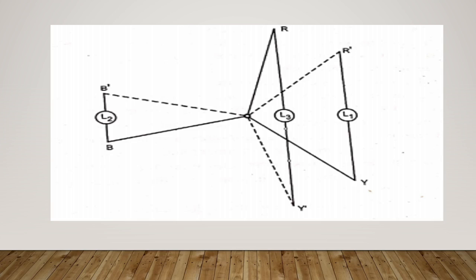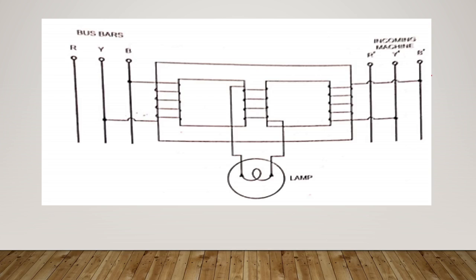Another method of synchronizing is with the help of one three-limbed transformer and a lamp, with the two primary windings on the outer limbs connected to the bus bars and the incoming alternator respectively, and the secondary winding on the central limb, like this. The correct moment for closing the paralleling switch is the middle of the dark period if the primaries are each connected the same way around, and the middle of the bright period if the connections of one winding are reversed.